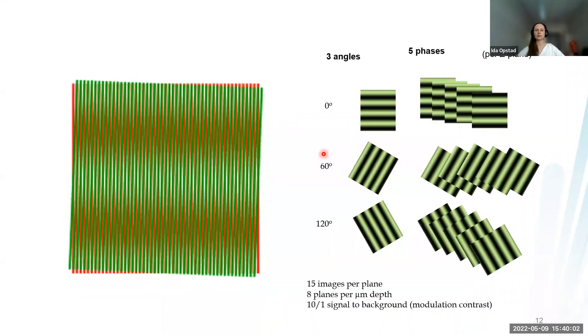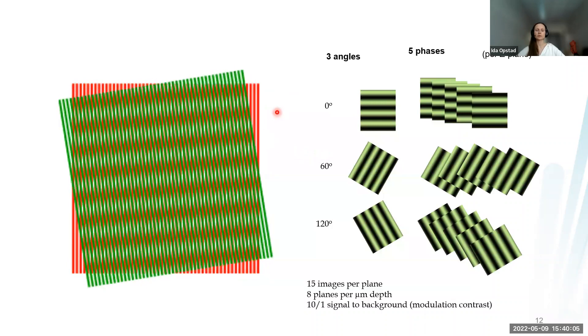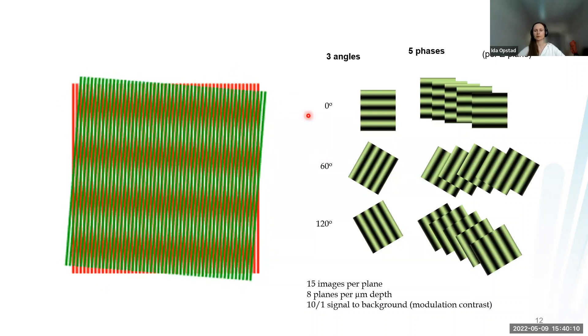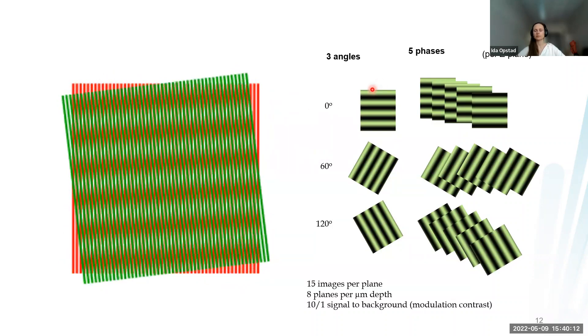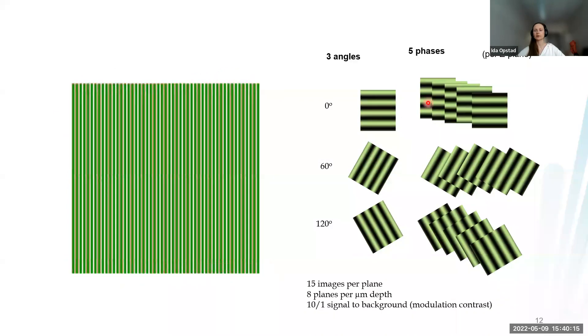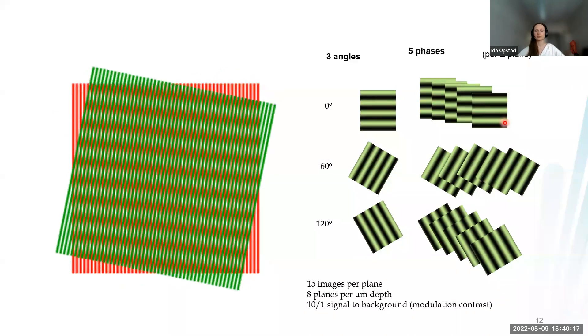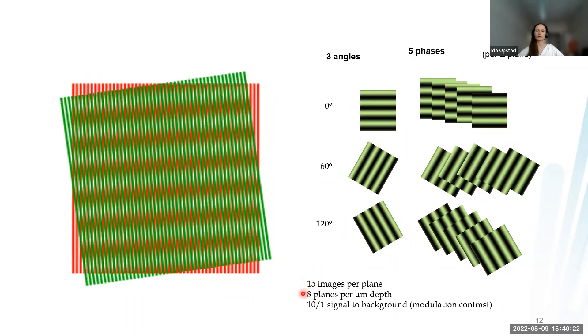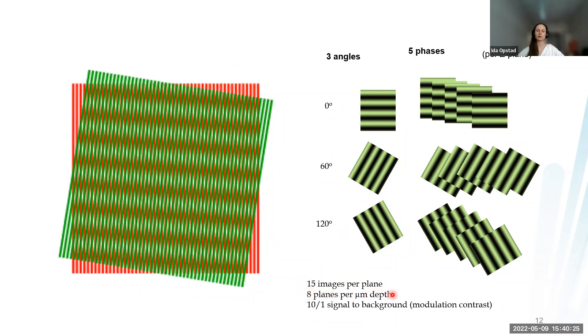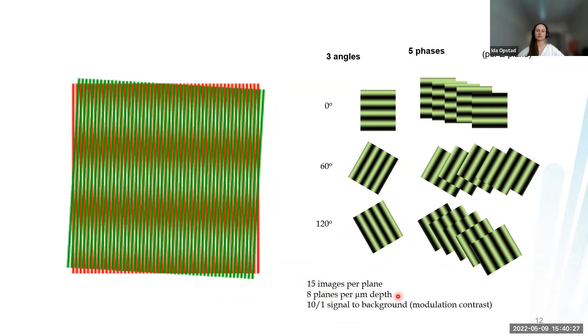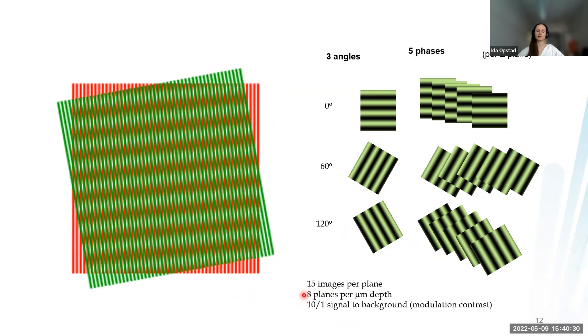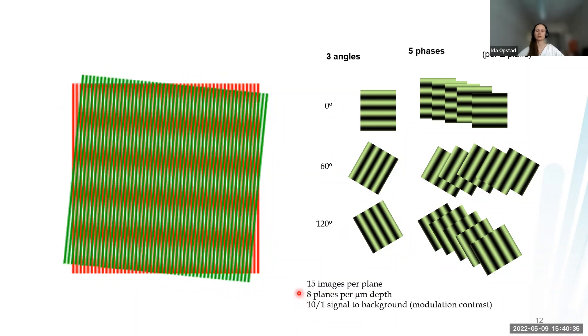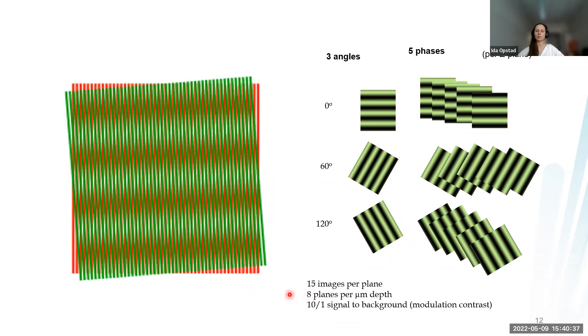In practice we use sinusoidal stripes as the illumination pattern. For the microscope I've used, we illuminate at three different angles and five different phase shifts. It's also a volumetric microscope where we use eight planes per micrometer depth. So we need 15 times eight images just to get one color channel for one micrometer volume.